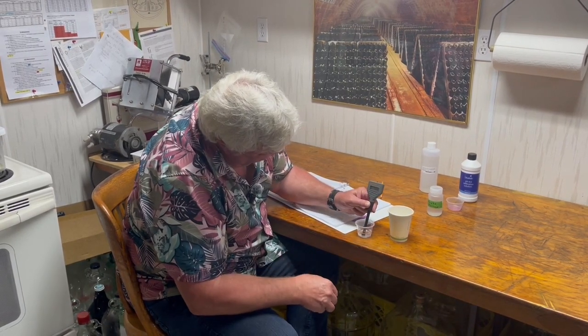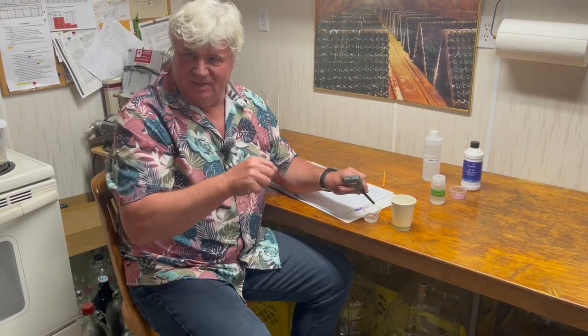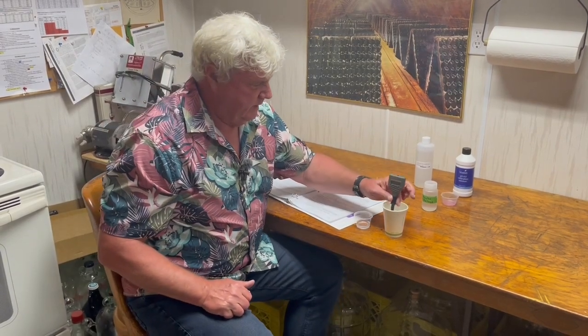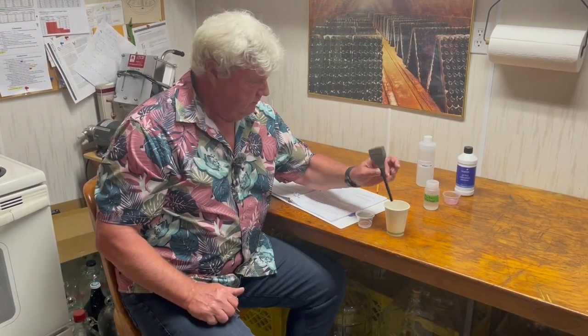Okay, there we got 7.00. Okay, so it's fully calibrated now. There's little adjustment screws here. It's like little volume controls or adjustments, so it changes the calibration factor inside there. One's the 4, one's the 7. Again, every pen is going to have a little bit different procedure, so you've got to just read up on it when you buy one. And they're not that expensive, $30 or $40 on the internet.